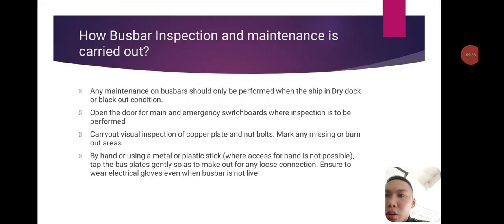Any maintenance on bus bars should only be performed when the ship is in dry dock or blackout condition. Open the door for the main and emergency switchboards where inspection is to be performed. Carry out visual inspection of copper plates and nut bolts. Mark any missing or burned out areas by hand or by using a metal or plastic stick, where access by hand is not possible. Tap the bus plates gently so as to make out any loose connection. Ensure to wear electrical gloves even when the bus bar is not live.